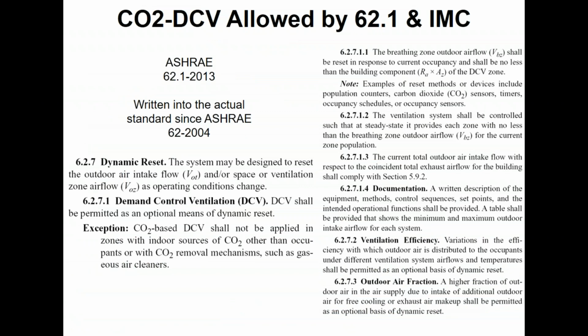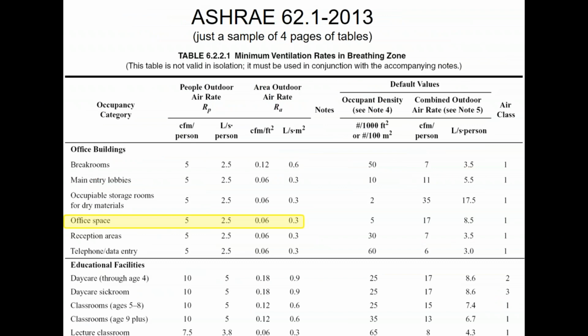CO2 is allowed by ASHRAE 62 and IMC, so it's sometimes required by IECC and required by 90.1. On the flip side, it's allowed by 62.1 and allowed by IMC, which makes sense because those codes need to be synced with each other. That's just the language showing you that CO2 is an acceptable means to reduce the ventilation rate below the otherwise code prescribed minimum. So you can go below the 1100 in my previous example, right? That example there, I can go below that. I modulate the people portion. I do not modulate the square foot portion, which is why these numbers got split. So I had 500 for the people in my example, and I had 600 for the square footage in my example. I would then modulate the outside ventilation rate between 600 and 1100.